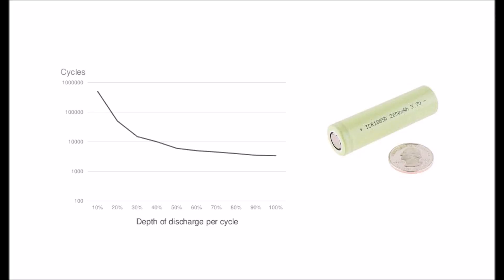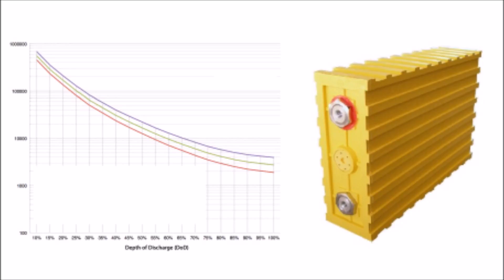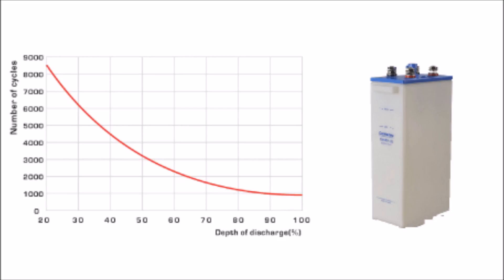This is true for every type of battery. Here is a lithium ion battery — at 10% depth of discharge, it delivers well over 100,000 cycles, dropping down to about 5,000 if you discharge it all the way to zero. Here's a lithium iron phosphate battery, which has the same problem. Although it can cycle more times overall, going all the way to zero still shortens the life greatly. And here's a nickel iron battery for good measure — same type of thing: the more you discharge it, the lower the life cycles.